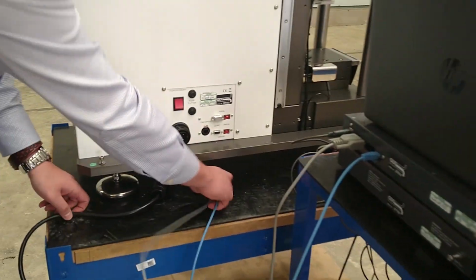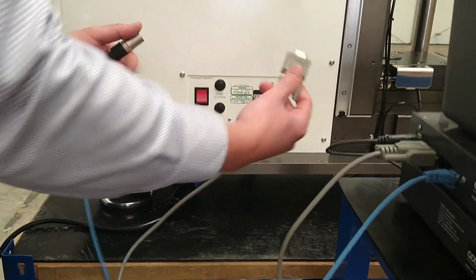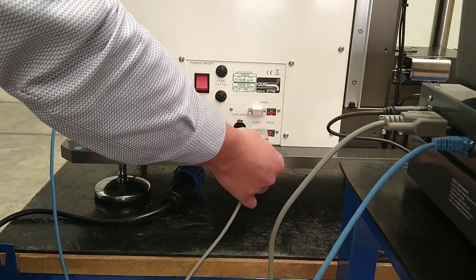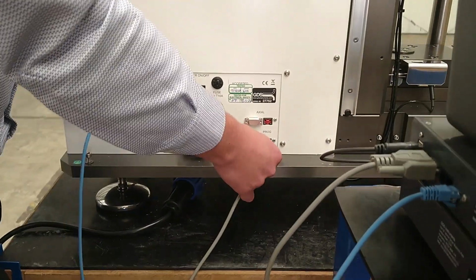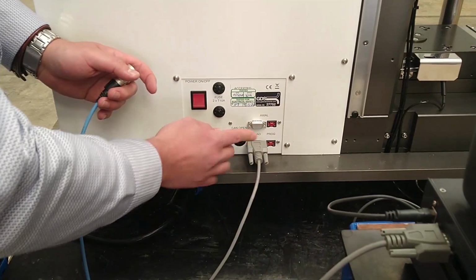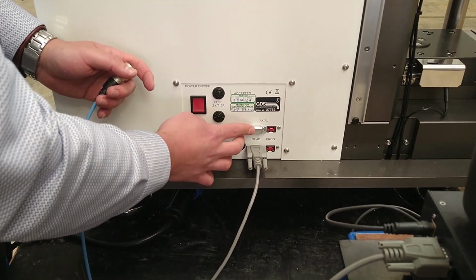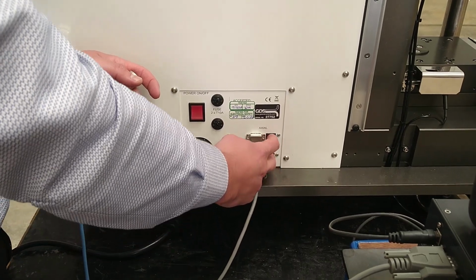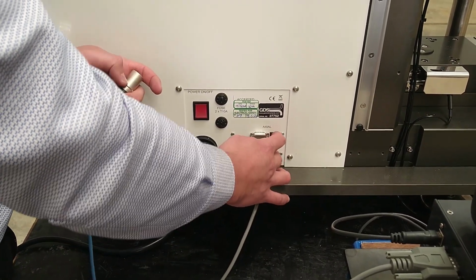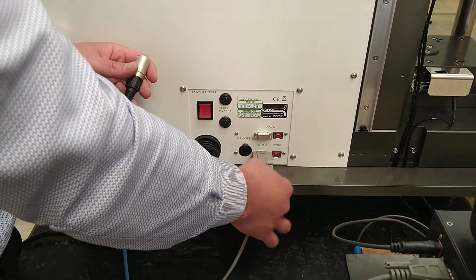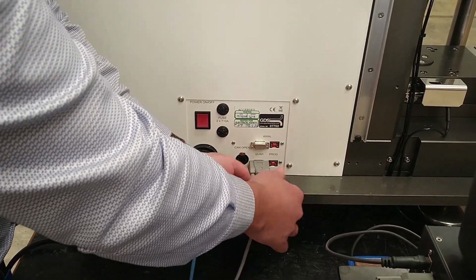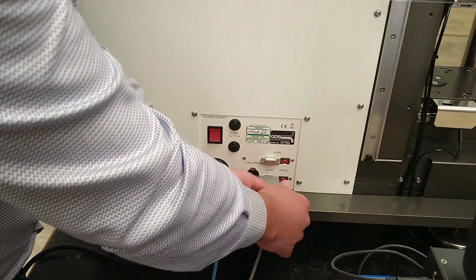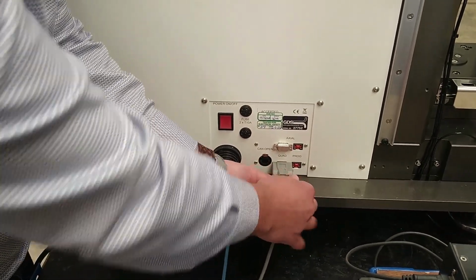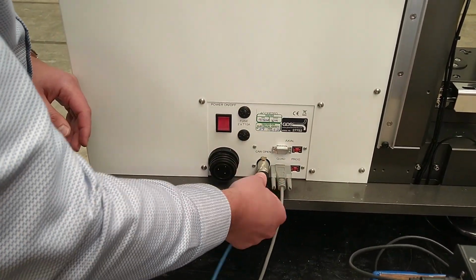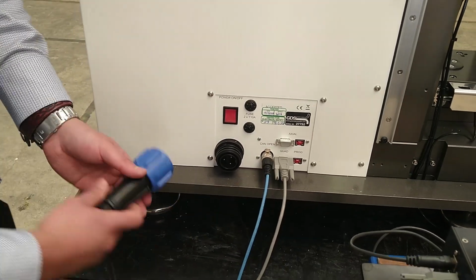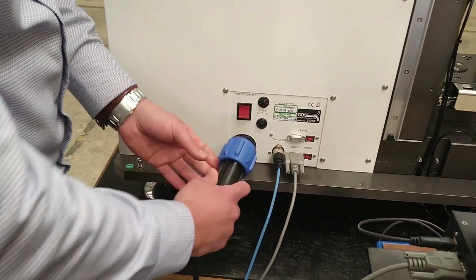On the machine side, we have the same cables, so we plug our quadrature for the shear axis, because that is the main axis in that machine. As you can see, the axial axis is blanked off, and two programming ports for the drives are also blanked off, because we only use them during the machine commissioning and testing. Can plug the CAN open cable, and the last part is plug the mains cable.